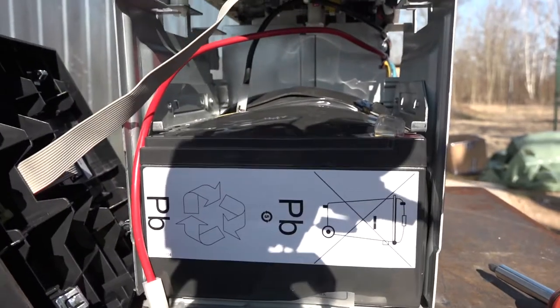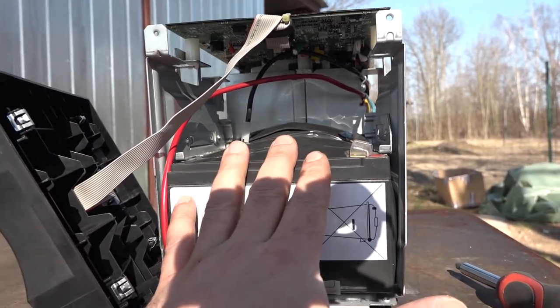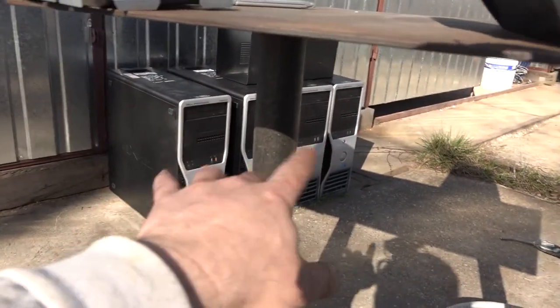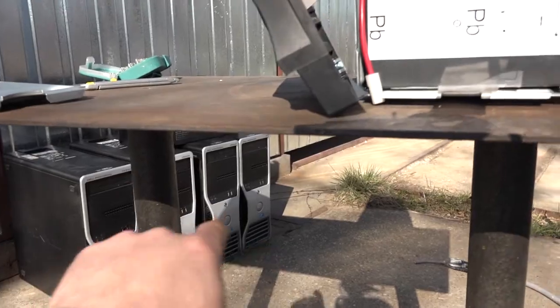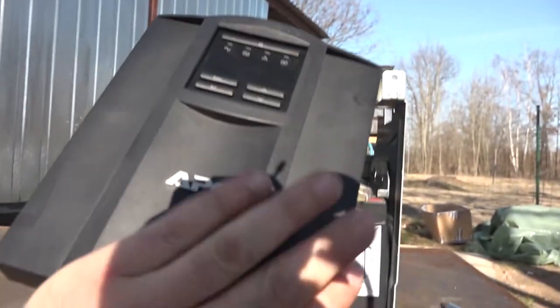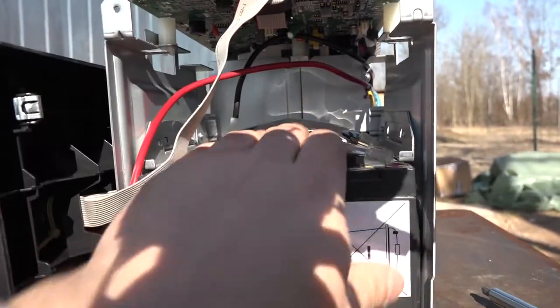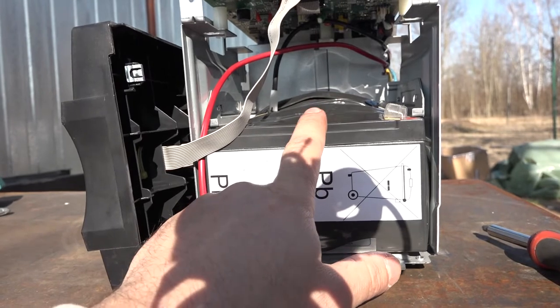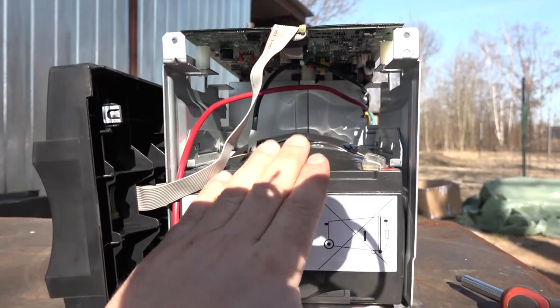I think those two batteries are already in a critical state. I think I'm kind of a lucky boy today because I detected this really bad smell, and also because my rendering farm system told me early in the morning that I had some kind of issue. So why am I lucky? Because I can imagine what could happen over the weekend if this dumb UPS 1000 system kept running for another 48 hours with these dead batteries inside, with this amount of generated heat.